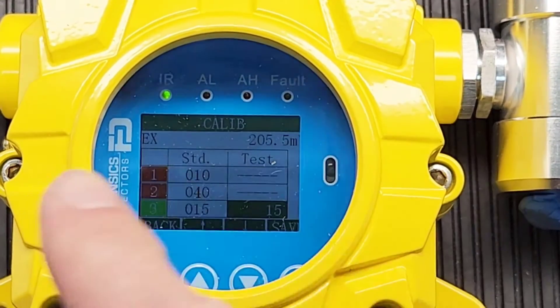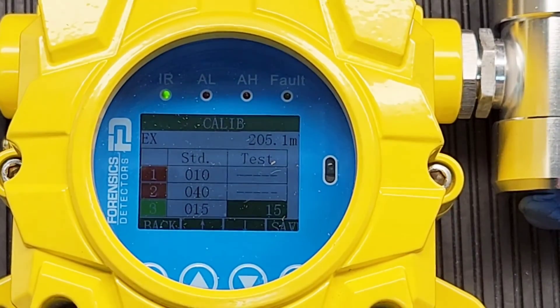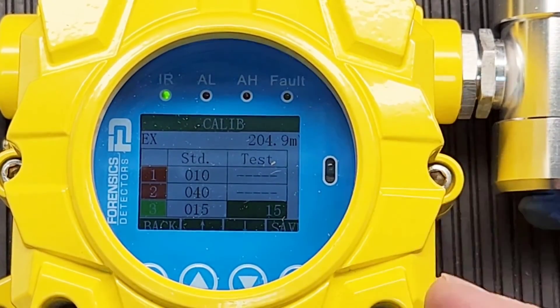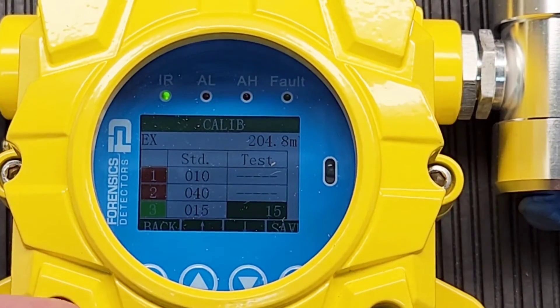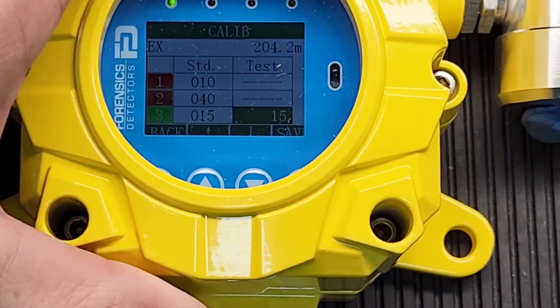We're doing it on the third point. Ignore STD1 and STD2 — ignore the first two lines. We want a simple two-point calibration: our first point was zero, and our second point is what we just did. Internally the unit shows three lines, but you go to the last line — simple as that. Press save and we're good to go. We've got a stable reading staying at 15.